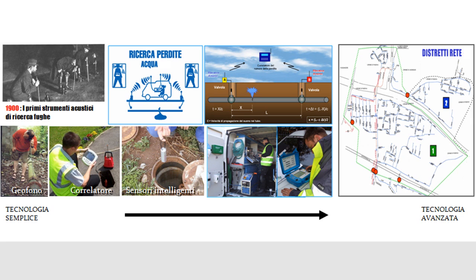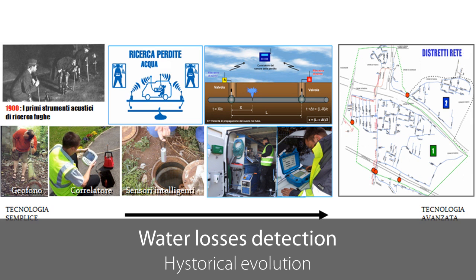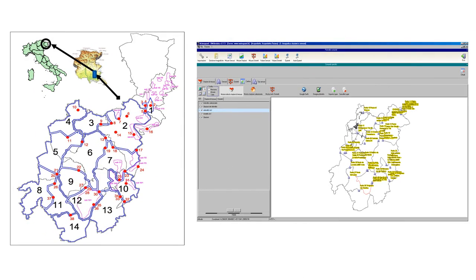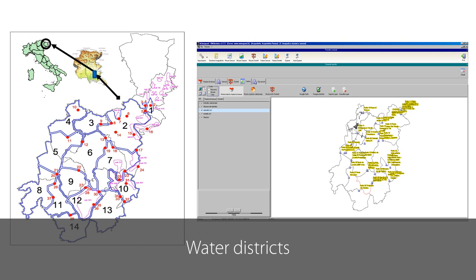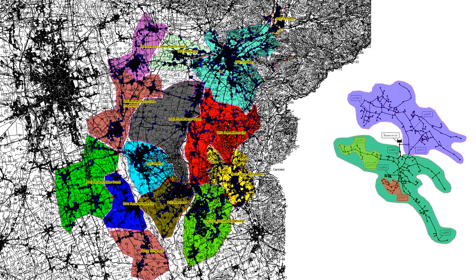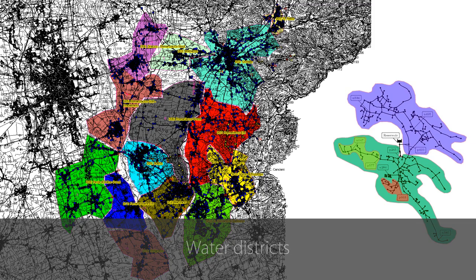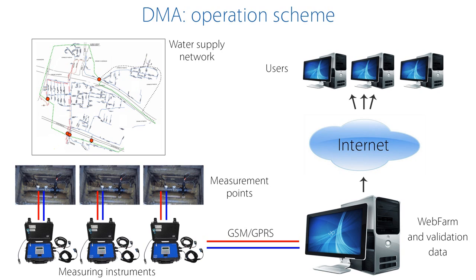This is an introduction about DMAs, the dedicated software WaterGuard, and the devices used for metering flow rates and pressures. Many changes took place in the last decades in water supply network management and the detection of water losses, reaching the cutting-edge approach based on the definition of physical and virtual DMAs. The DMA is an area of a distribution system which is specifically defined — for example by the closure of valves — in which the quantities of water entering and leaving the district are metered by suitable instruments for flow and pressure measurement. A district should be homogeneous, of limited territorial extension, and have similar hydraulic features.